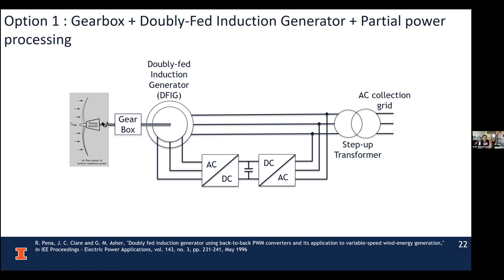So with a gearbox, a doubly fed induction generator, and then there's something called partial power processing. What do I mean by that? Think about it this way: imagine there is a 10 megawatt wind turbine. So there is 10 megawatt of power coming into this mechanical port. Majority of this power can be directly fed from the generator to the grid without being processed by the power electronics. Part of the power has to be processed because we need some kind of control, otherwise we won't achieve maximum power point tracking. So this power converter, if we operate with limited speed range, can be reduced almost by 60%.